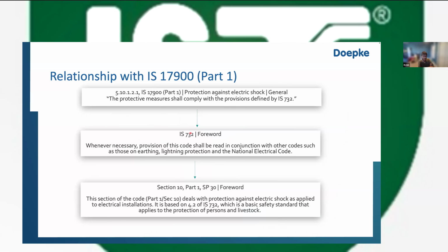So what is the relationship between these standards and IS 17900? In the presentation, I'm going to be talking largely about IS 732 and the NEC. But the important thing is that these are actually integral within 17900. If you look at clause 5.10.1.2.1 in IS 17900, which is protection against electric shock generally, it says that the protective measures shall comply with the provisions defined by IS 732. So with regards to protection against electric shock, you have to comply with IS 732. In IS 732, it says, whenever necessary, provisions of this code shall be read in conjunction with other codes, such as those on earthing, lightning protection, and the National Electrical Code. So 17900 says you have to follow IS 732, and IS 732 says that it shall be read in conjunction with the National Electrical Code.